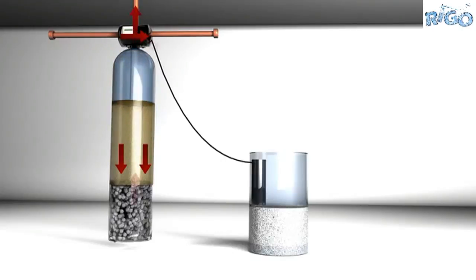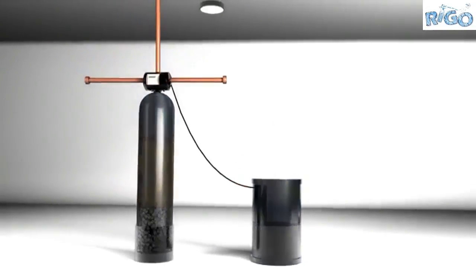While this is happening, we are also sending water down the fill tube to replenish the brine tank. On a 1.5 cubic foot system, this process takes 9 minutes. For every 2 gallons of water that goes to drain, a half gallon will go to the brine tank. This completes the process of regeneration and gets the brine tank prepared to regenerate the resin in the future.